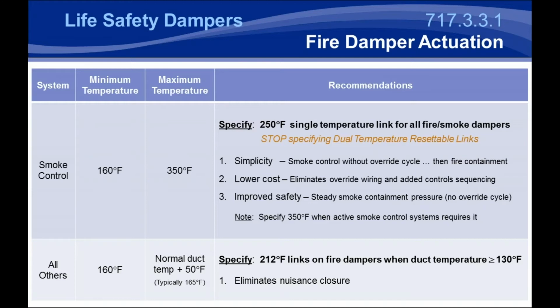Now, for all of the fire dampers that are in a smoke control system, there is an allowance for a minimum set temperature of 160 degrees and a maximum temperature of 350 or 250 degrees, depending on what that smoke control system is set for.